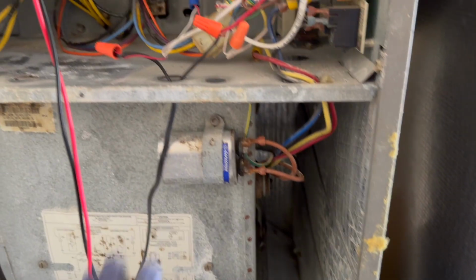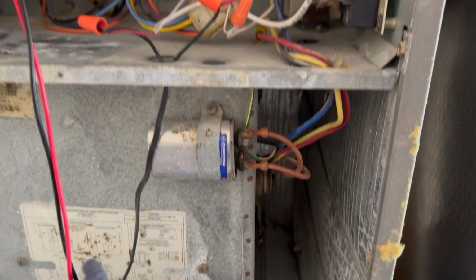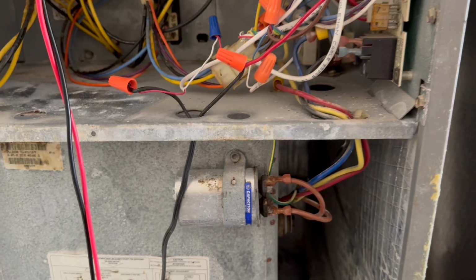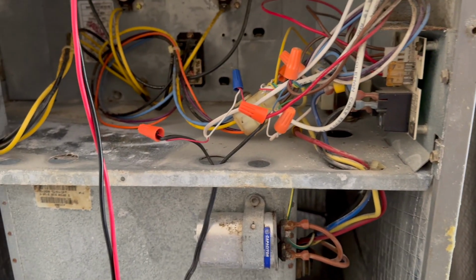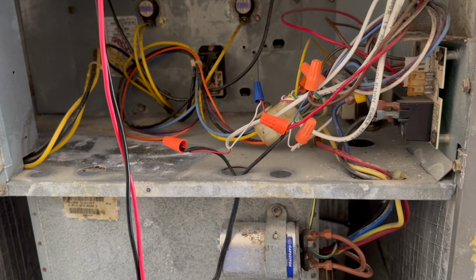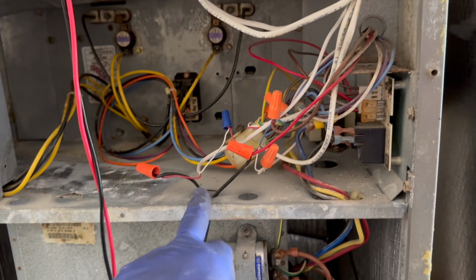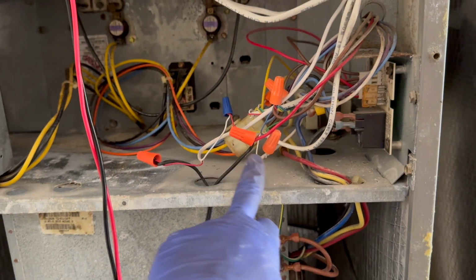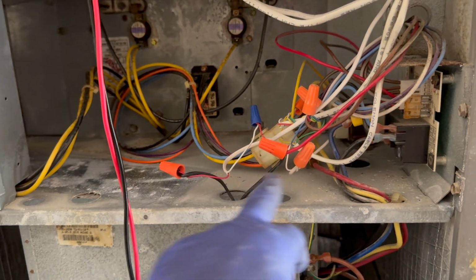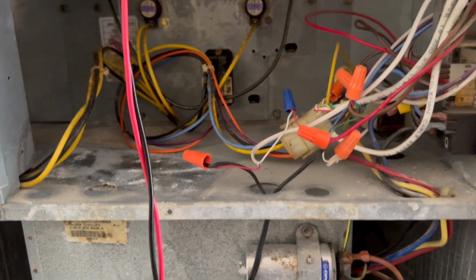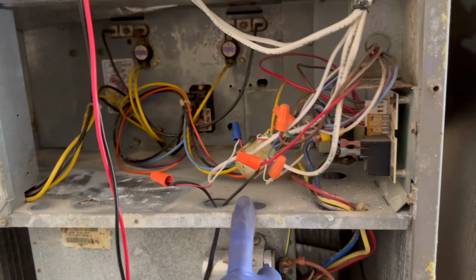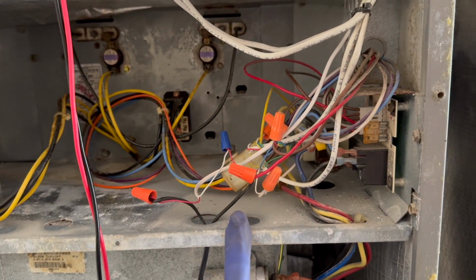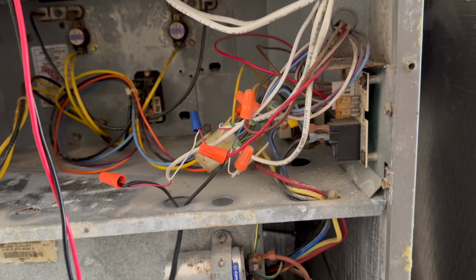Now, the reason I did not come to the float switch right off the bat is sometimes this float switch is connected differently, so you don't know what AC you're troubleshooting and what kind of setup it has. In my case, this particular one is jumped through, kind of like in series. If it was in parallel, you wouldn't have that issue, but you cannot have this connection in parallel.